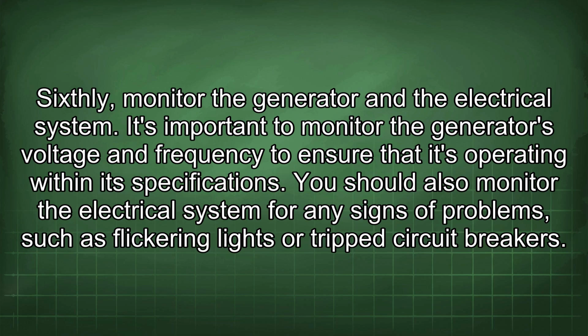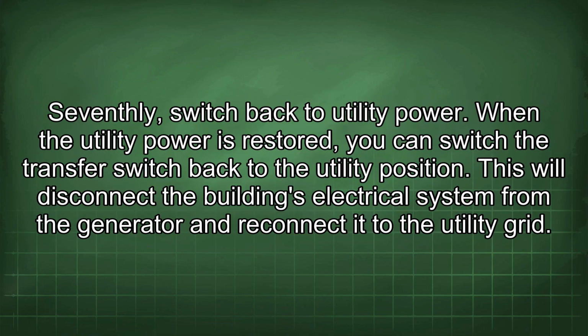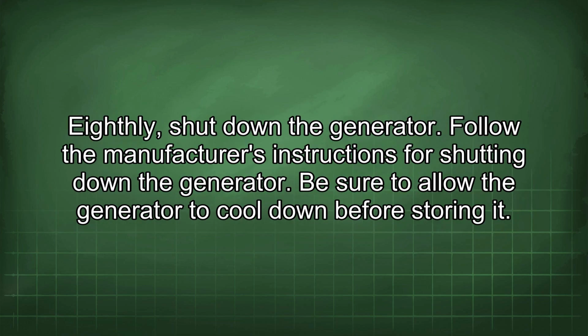Sixthly, monitor the generator and the electrical system. It's important to monitor the generator's voltage and frequency to ensure that it's operating within its specifications. You should also monitor the electrical system for any signs of problems, such as flickering lights or tripped circuit breakers. Seventhly, switch back to utility power. When the utility power is restored, you can switch the transfer switch back to the utility position. This will disconnect the building's electrical system from the generator and reconnect it to the utility grid. Eighthly, shut down the generator. Follow the manufacturer's instructions for shutting down the generator. Be sure to allow the generator to cool down before storing it.